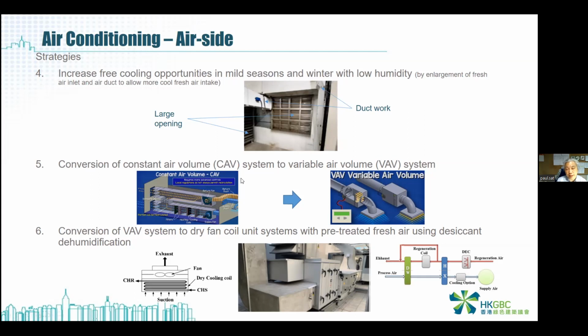And the fifth one is also very common, which is to convert the constant air volume system to a variable air volume system. When you do the conversion, the most serious point is that you need to install the variable air volume boxes, the VAV boxes, in the ceiling void. It depends, because I see that in some buildings with open plan offices, they may not need to install the VAV boxes on the whole floor. The VAV boxes are only used in meeting rooms or boss rooms, something like that.